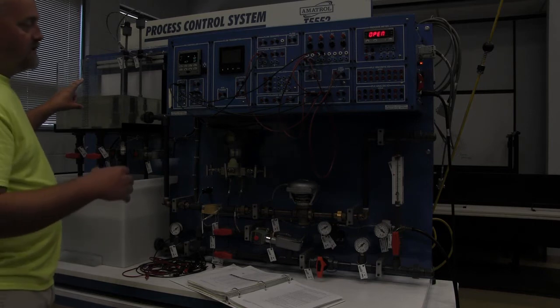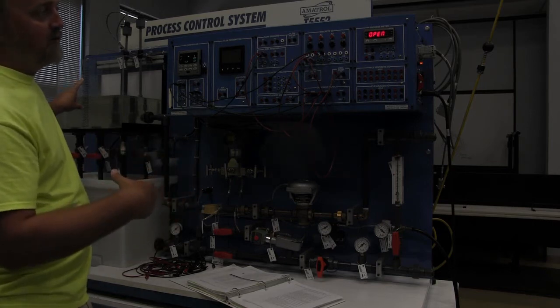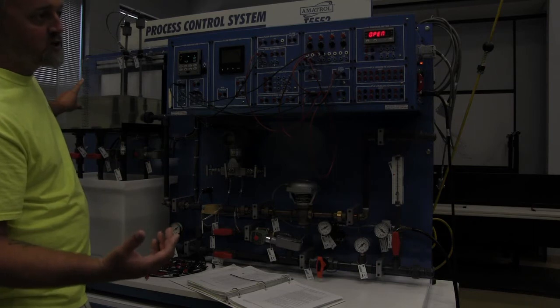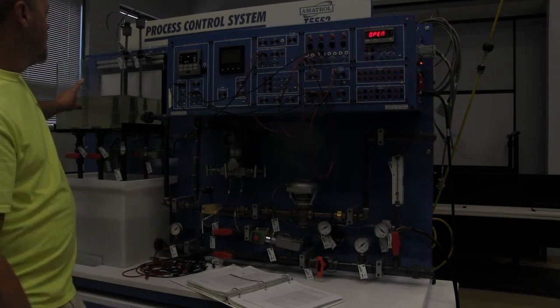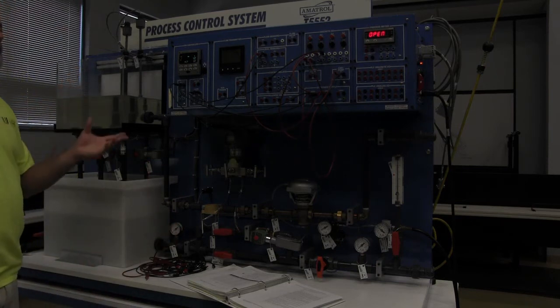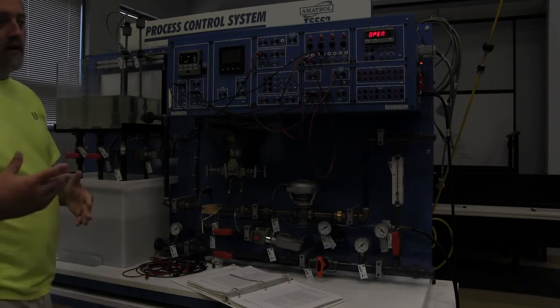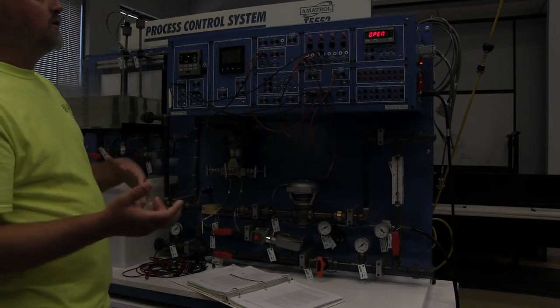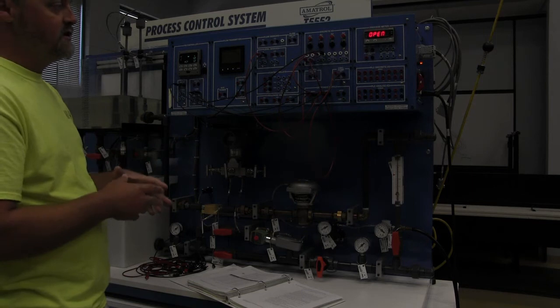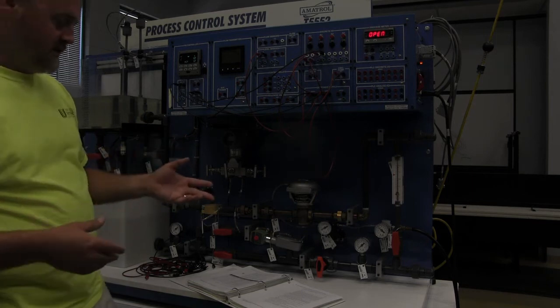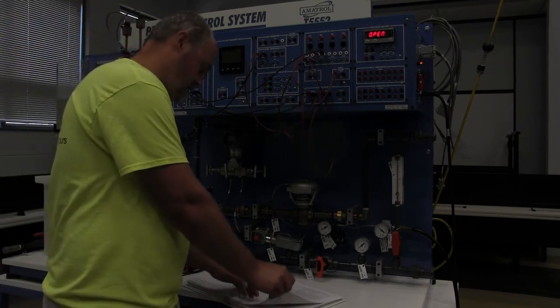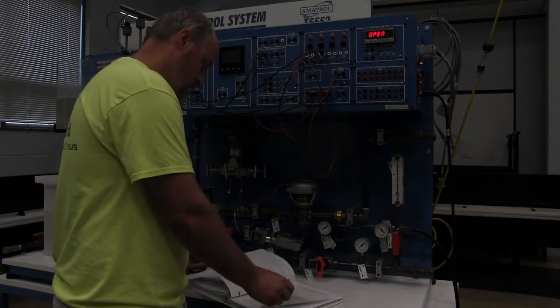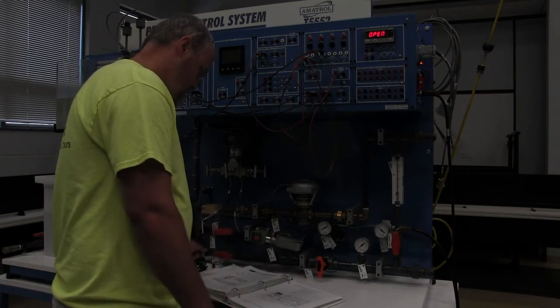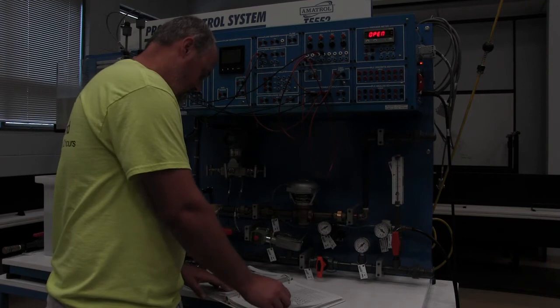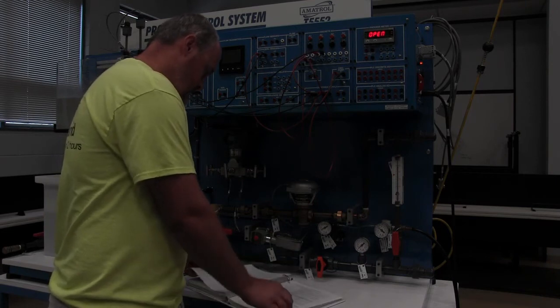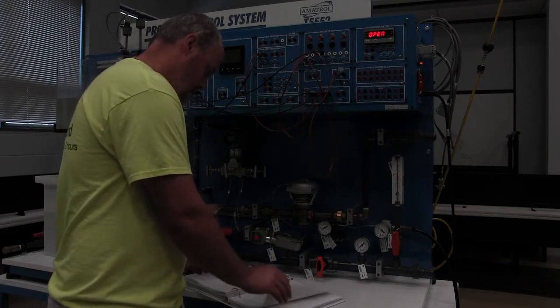And control our tank level, and if for some reason the pump didn't shut off or didn't come on, once the level gets outside of that window, it would go into an alarm state. That would alert you that there's something going on with this equipment or device, that you've got trouble and someone needs to get there and take a look and see what's going on. Let's see here what we got.